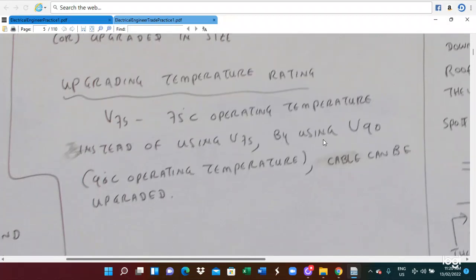Upgrading the temperature rating: V75 is a 75 degrees centigrade operating temperature. Instead of using V75, you can use V90. If the cables are derated, you can increase the cable size or utilize cables with an upgraded temperature rating. If only a single cable is installed in the circuit, it is not a problem.